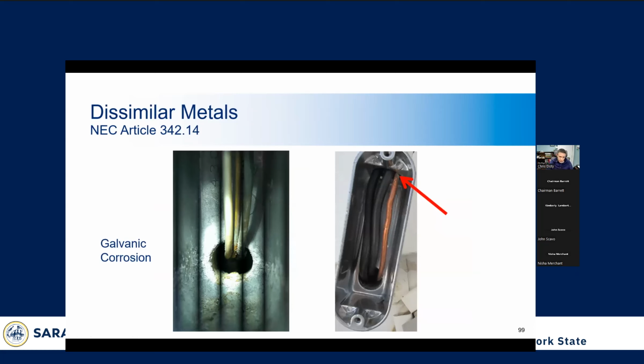Here we have a situation where we see what's called galvanic corrosion, and that happens with the direct contact of dissimilar metals. We saw that with the aluminum panels and the copper lugs. So here both of these situations are showing how much corrosion you can get. This one's not as good. You can barely see it up here, but you can see the copper and this fitting, which is probably aluminum, are in contact and it's causing corrosion. And then here you can see a much worse version of that where there's corrosion occurring. This is in a pretty wet environment, so that helps it corrode faster. And a way to avoid this would be to use insulated conductors, and there's other methods too.